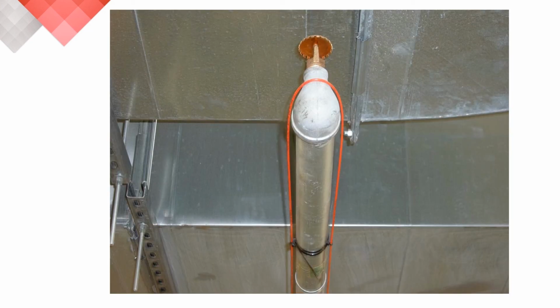In many cases, for ceiling detection, the Protectowire is attached to and parallels each sprinkler branch line. At the end of each branch line, the detector is gently turned, maintains our 2.5 inch or 6.4 centimeter bend radius across and moves to the next adjacent branch line and then proceeds back in the opposite direction.